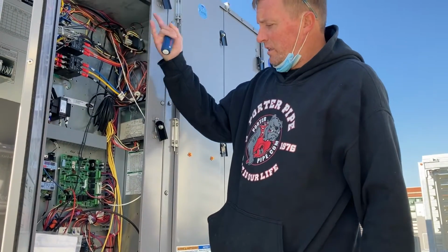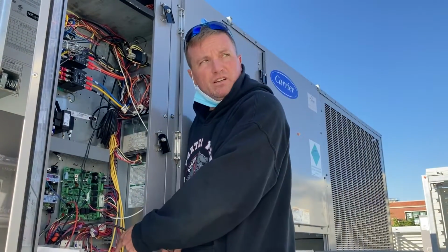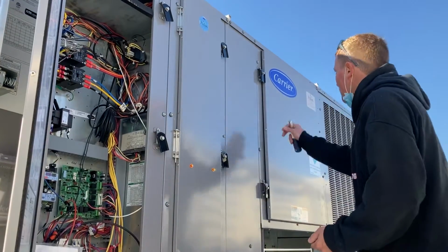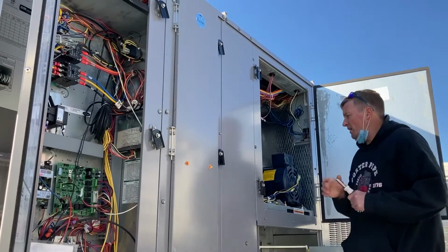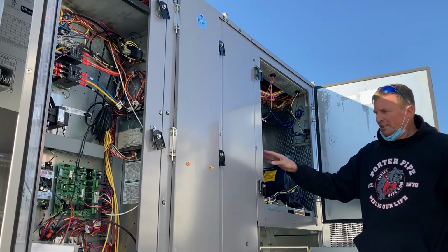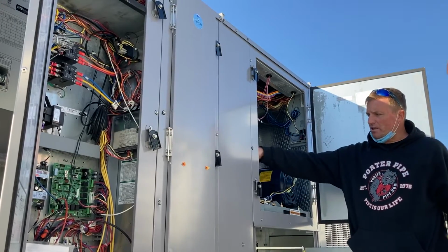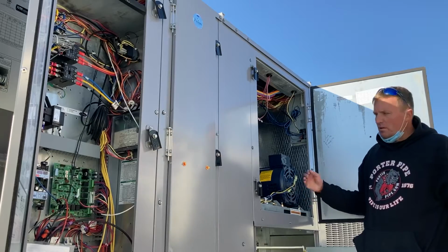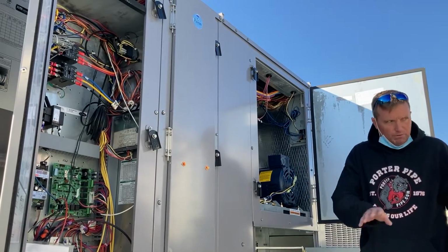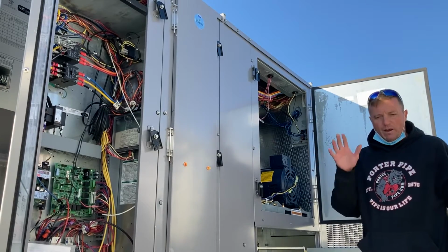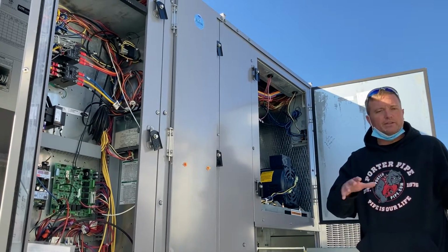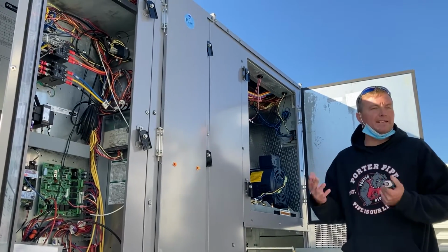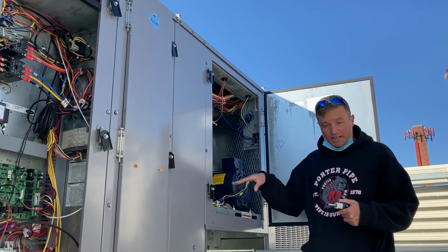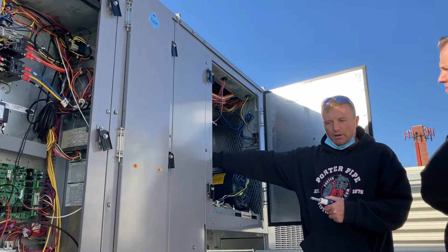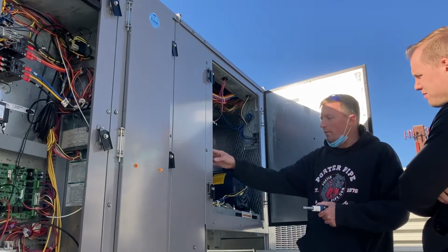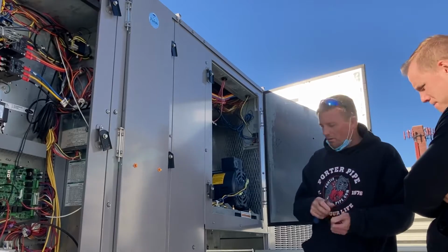Contactors for the compressors, and the fan is driven by the VFD, so you're not going to have any contact or anything as far as that goes. In the event that your VFD is down and we can't get air, these 3 wires here have jumpers. These 3 have jumpers. Jump it together and it'll just run full blast. We have to be careful because you have VAVs, so we need to make sure that the VAVs are opening so we don't explode ductwork. I doubt we would, but for safety reasons, if we do this because there's something wrong with the drive and we find it's dead, and we need to get air, we need to make sure the box is open, okay?